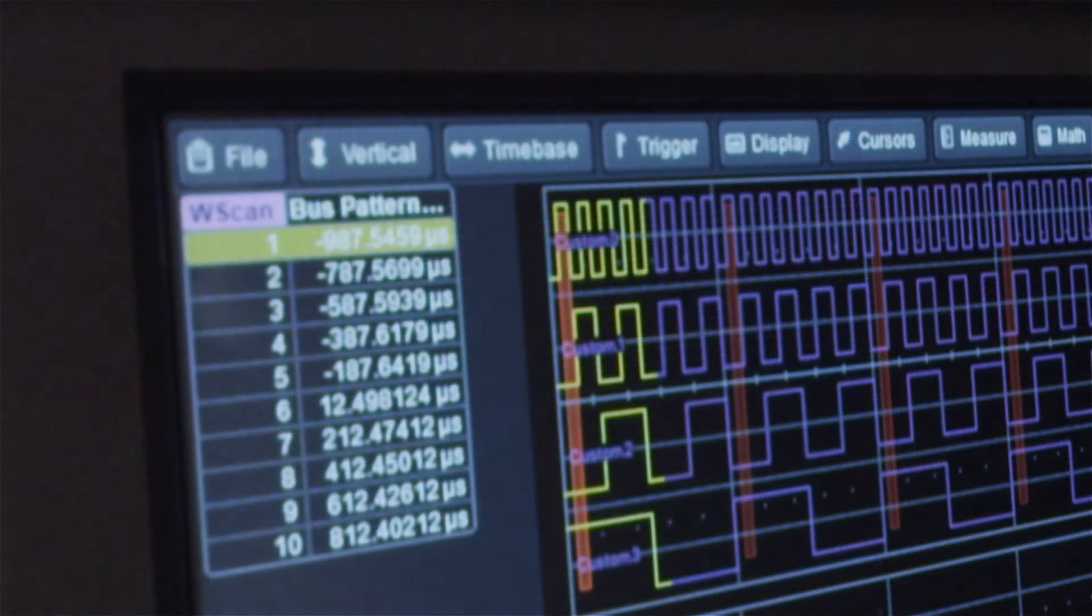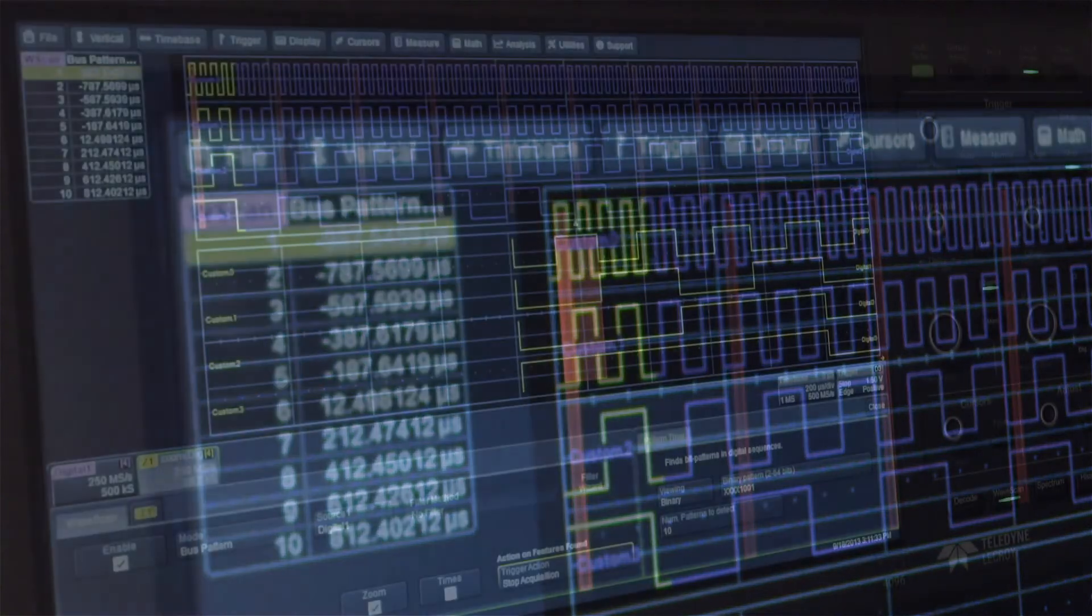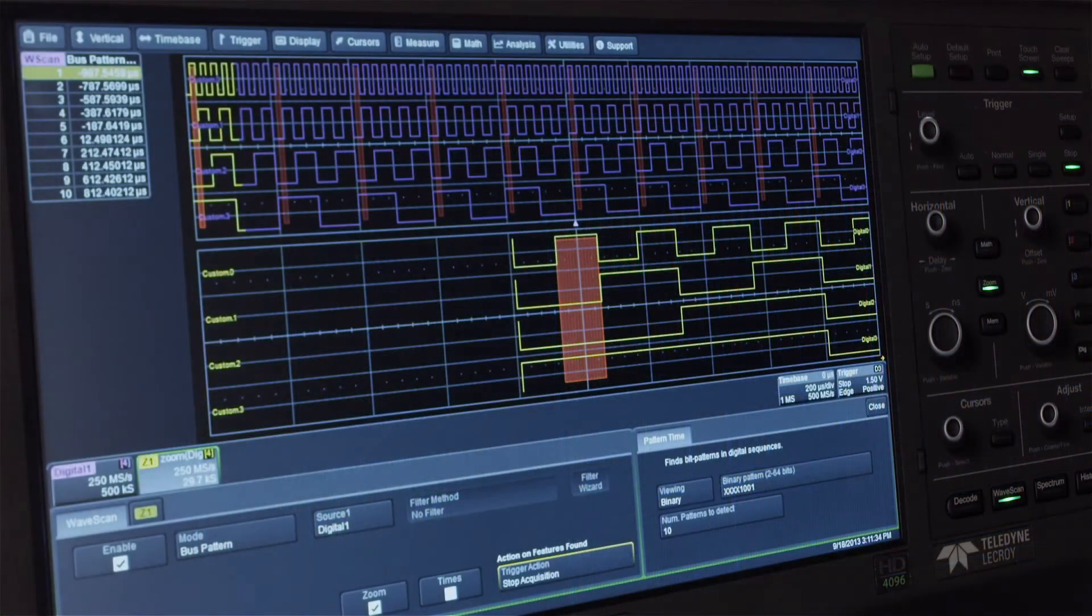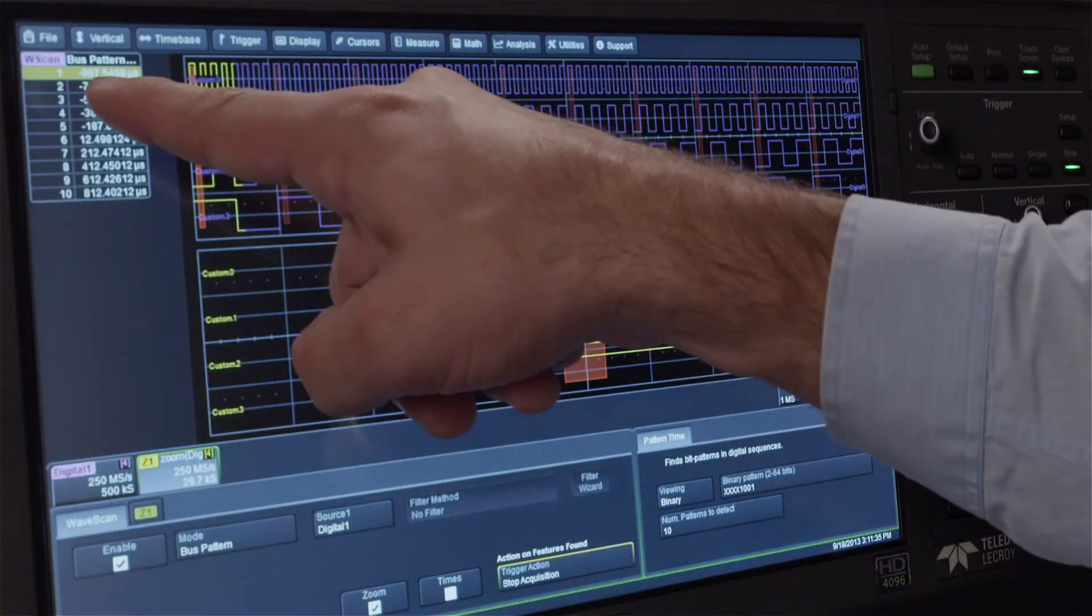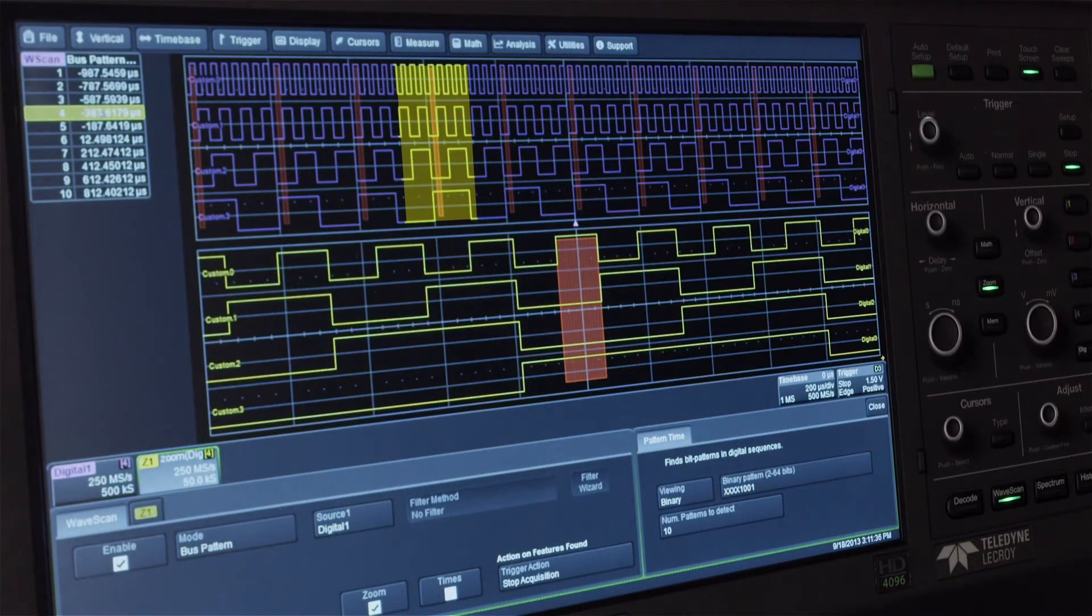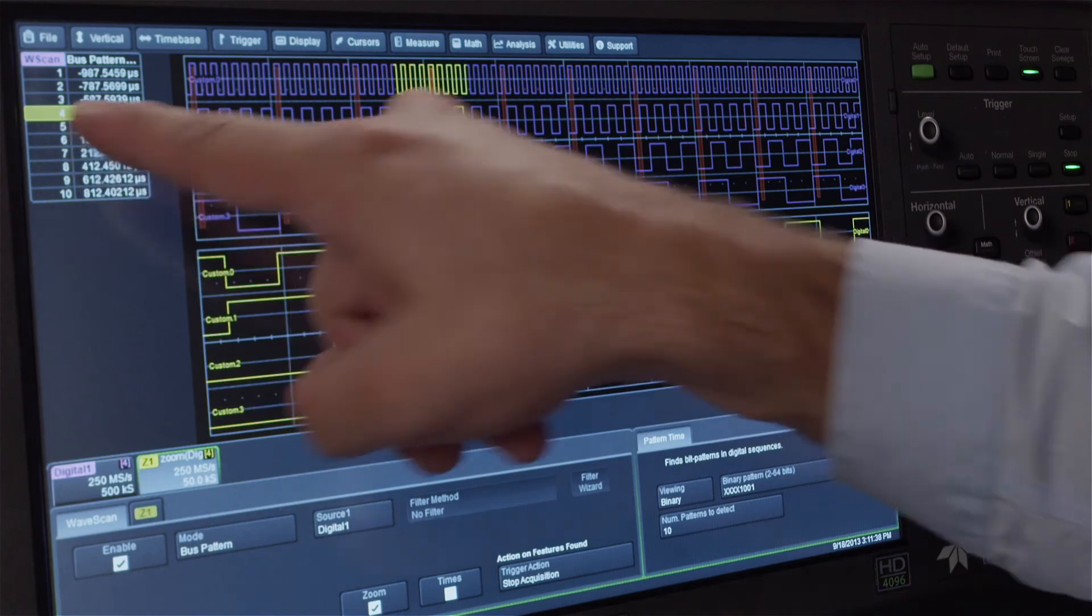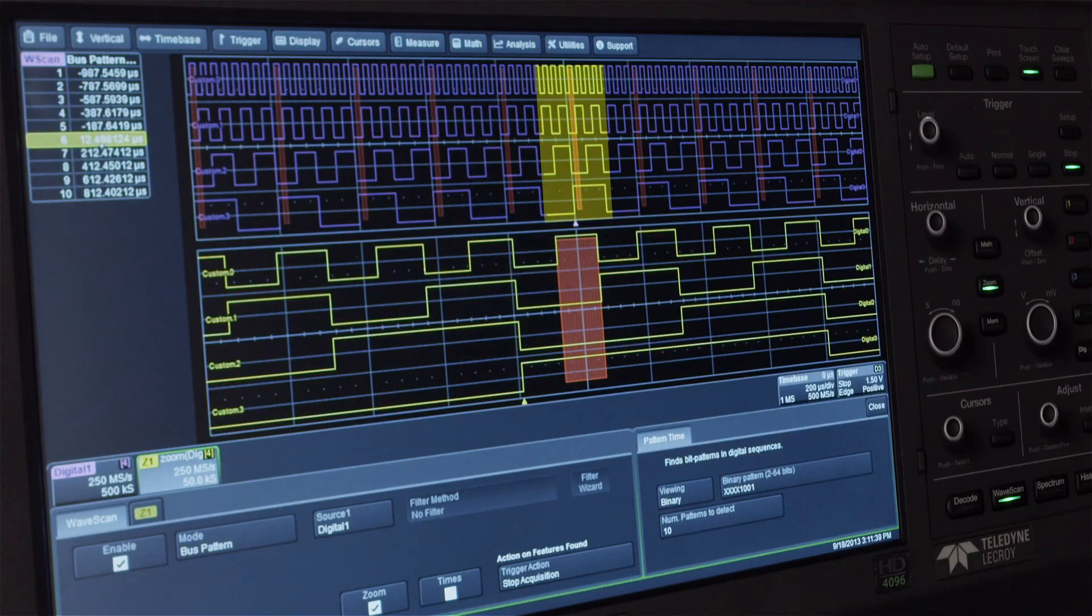Notice that 10 instances of the pattern have been highlighted and displayed in the table on the left side of the screen and Wavescan has stopped the trigger. Selecting any entry in the table automatically zooms to that instance.